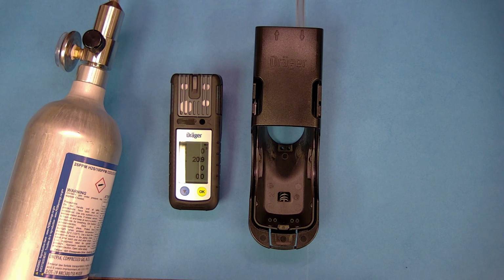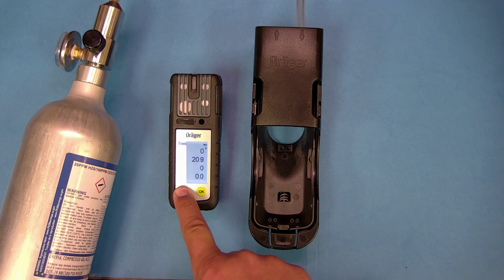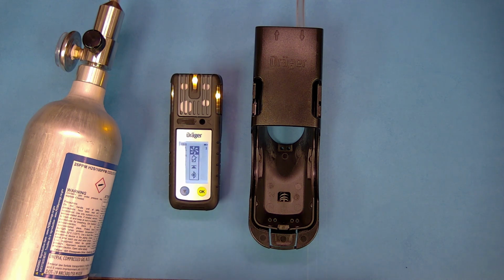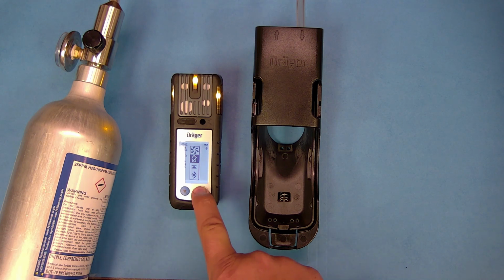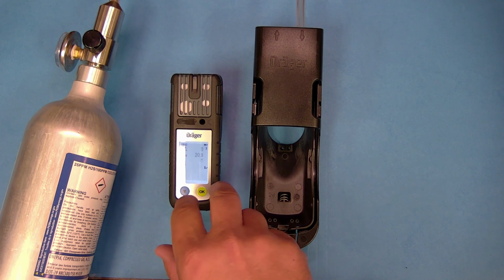To access the bump test icon in the quick menu, you're going to press the blue button 3 times like we did back for a 0 calibration. You're going to be looking for the icon with a cylinder of gas and the check in the middle of it, which is our second icon. Press the blue button once to highlight that, and then you're going to press OK and insert the device into the calibration adapter.